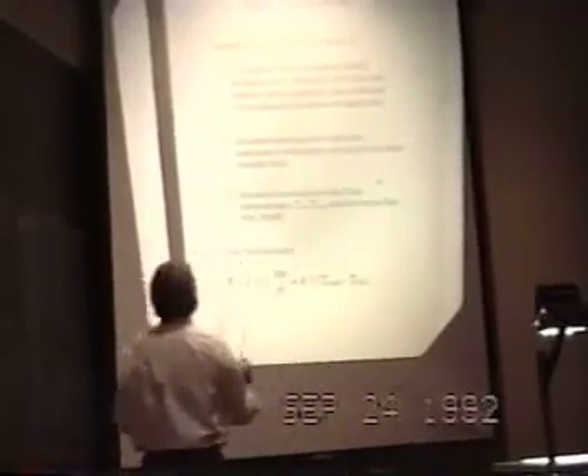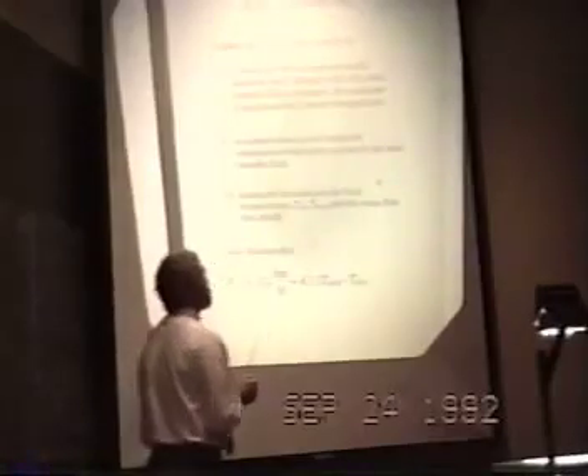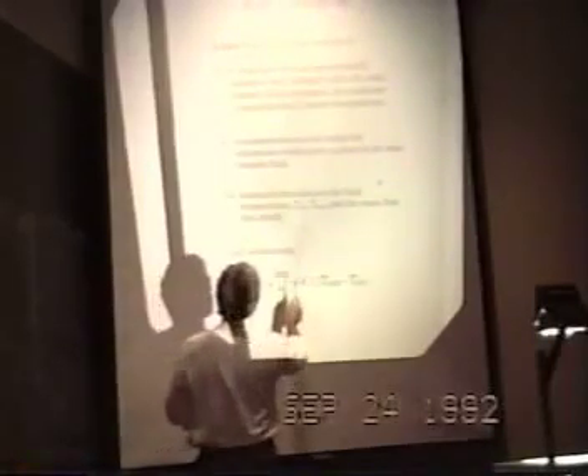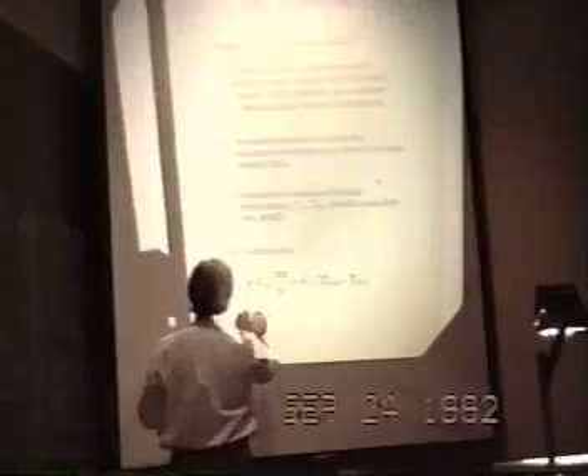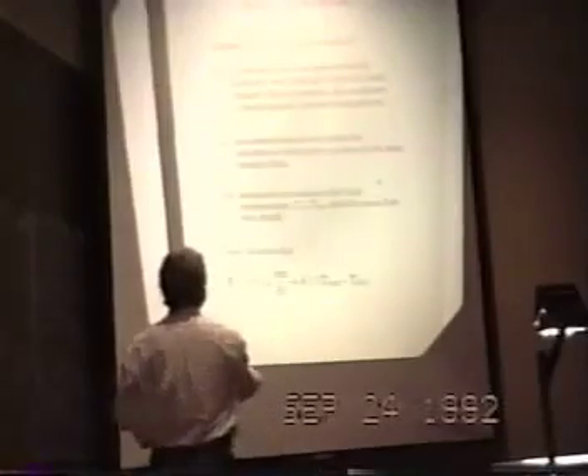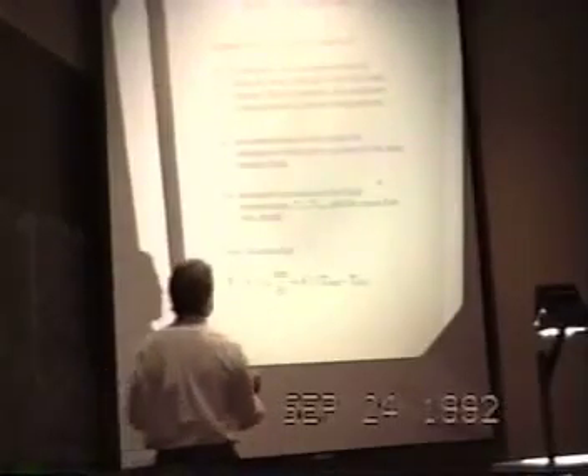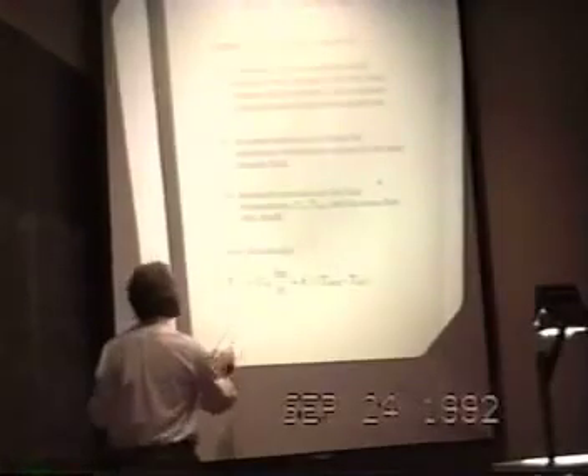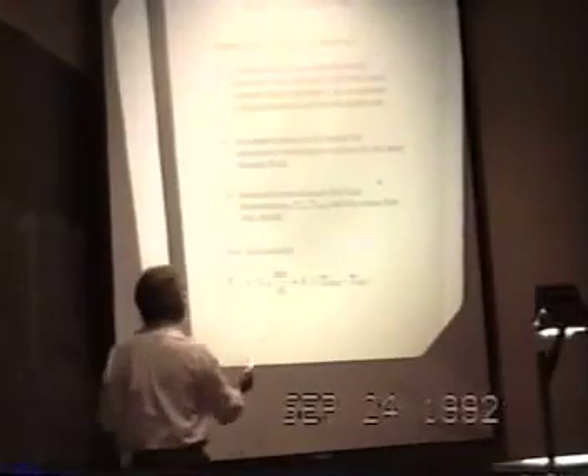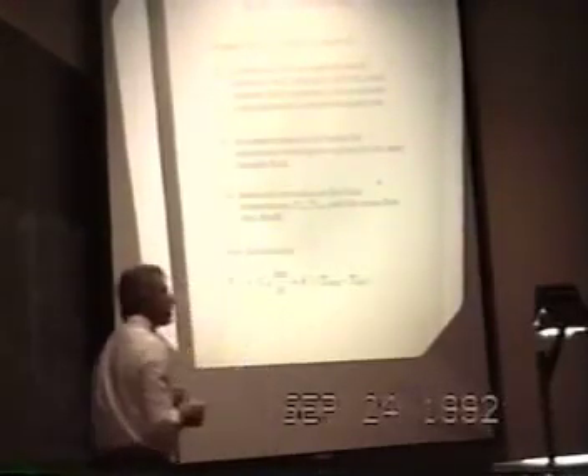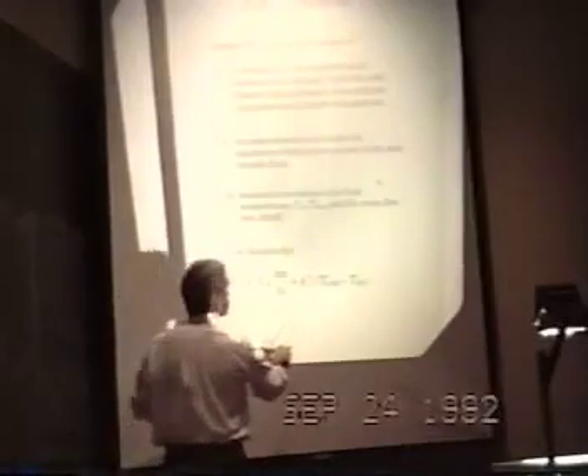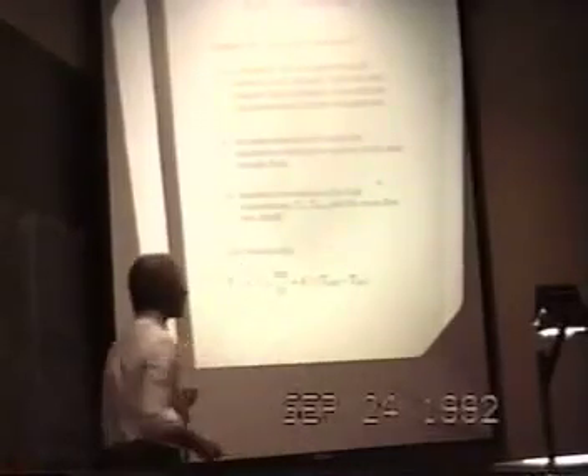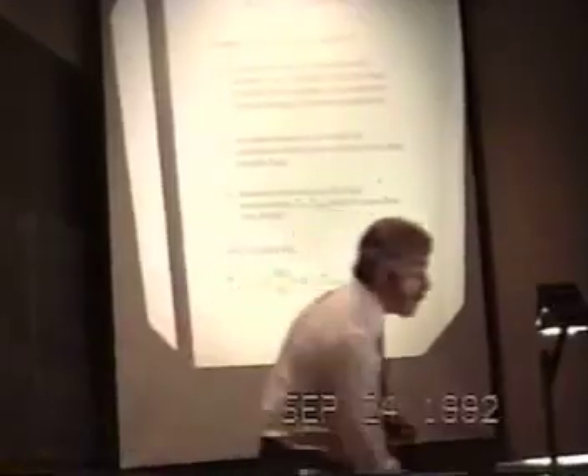So the sensitive parameters, the parameters which might be subject to systematic errors, are the inlet temperature, the outlet temperature, and the mass flow rate, so that the power measured by such a calorimeter involves the heat capacity of the fluid, the mass flow rate, a conductive loss term as that fluid loses heat to its environment, and the inlet and outlet temperatures. This is the only equation which governs the steady state operation of this calorimeter.